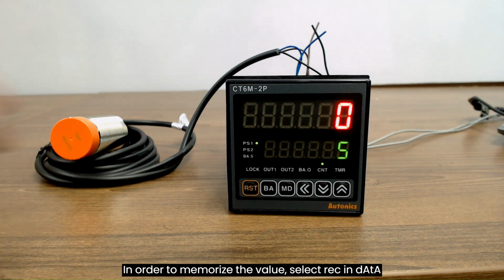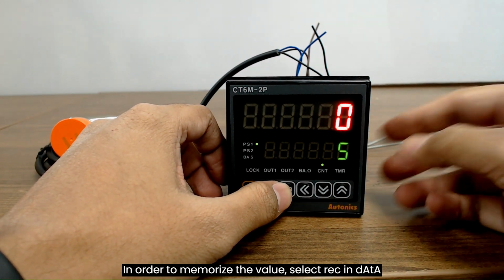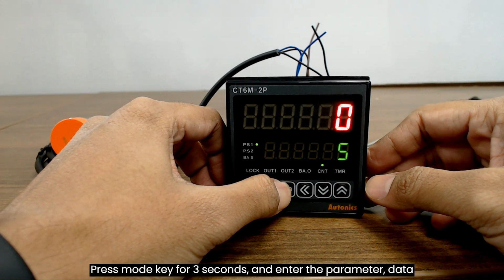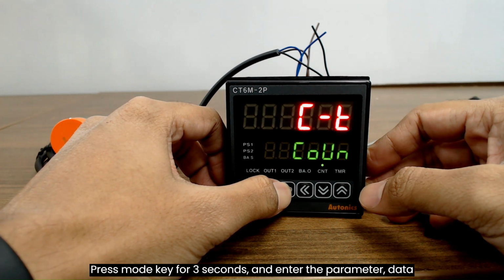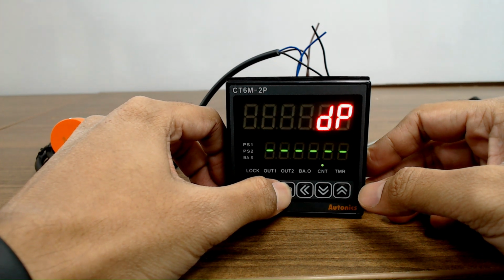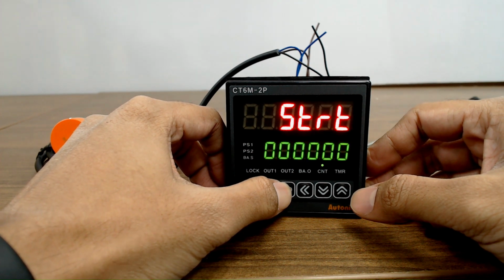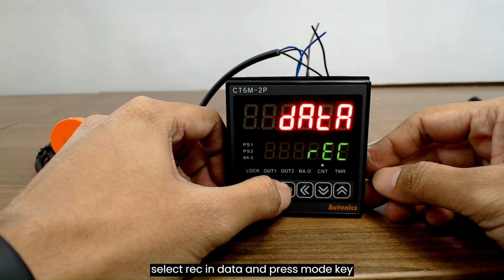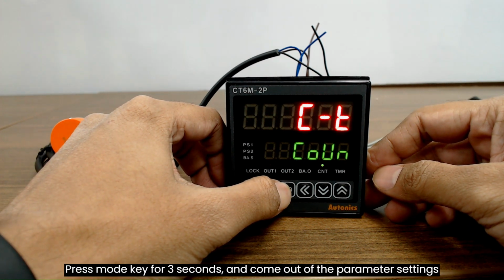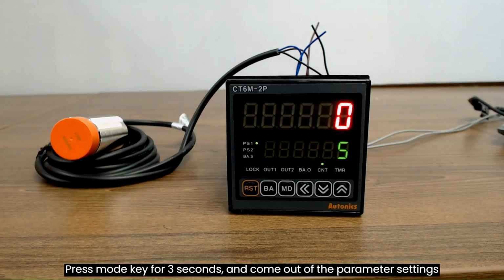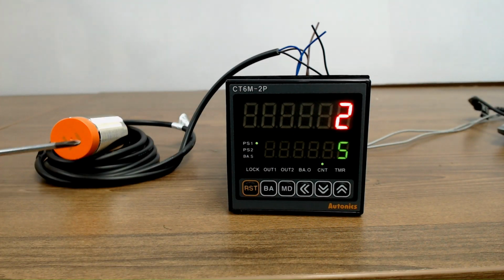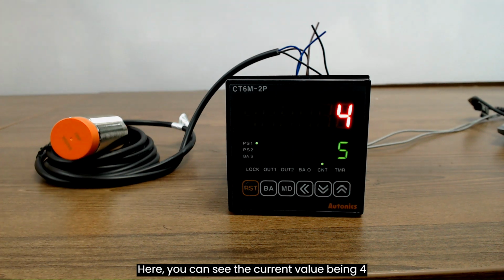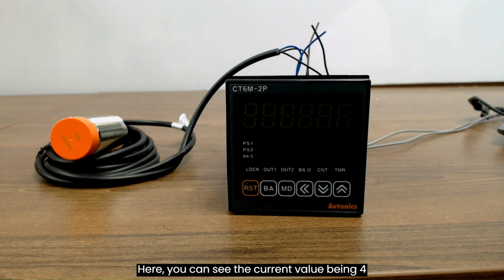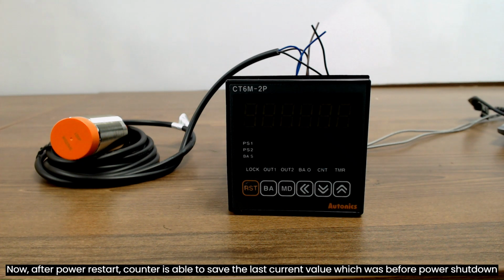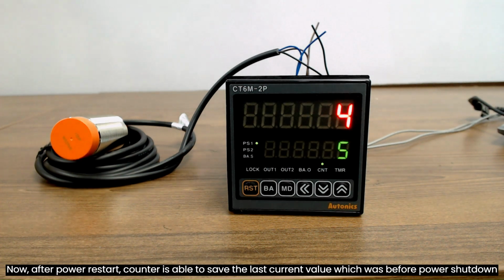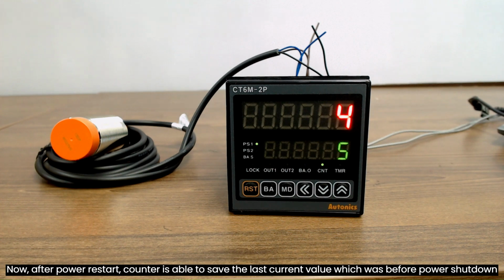In order to memorize the value, select Record in Data. Press mode key for 3 seconds and enter the parameter data. Select Record in Data and press mode key. Press mode key for 3 seconds and come out of the parameter settings. Here you can see the current value being 4. Now, after power restart, counter is able to save the last current value which was before power shutdown.